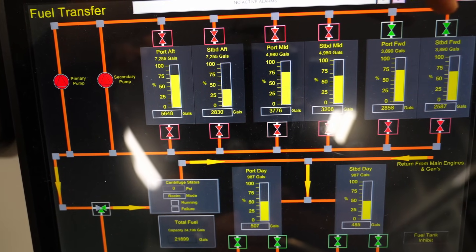I just spoke to the dock attendant. The maximum flow we can do is 50 gallons per minute. However, that is not how we're going to start. We normally start at 25 gallons per minute for the first 10 minutes, just to make sure we have the right tank selected, that all the valves are open, and that we don't have any drips or leaks.